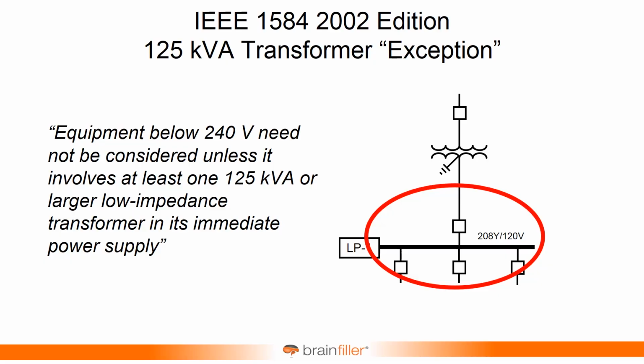So what this was all about is if you're performing arc flash calculations on the secondary side of a small transformer at 208, and let's say the arc flash occurs somewhere between the main and the transformer, or the main piece of equipment. Normally what you're going to do is you're going to look at the duration of the arc flash being defined by a device upstream, which would be a primary. And you start looking at how long it takes a primary device to operate. It could be a while.